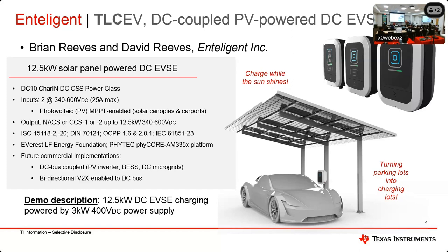Yes, sir. A little more specific: if I buy the latest generation Tesla Solar and Tesla Powerwall with the gateway, hardware-wise, does that have that kind of DC bus at the same time? So it does accept. The bus is a 48-volt bus, so our solution doesn't boost up from 48 volts. I was surprised that with the Powerwall 3, I guess they use a 48-volt battery system because it's smaller and they can get it all into that package. But if you look at the round-trip efficiency to store onto their battery, they're losing 10%, even though it's DC coupled, because they're going from 400 volts to 48 volts and back and forth.